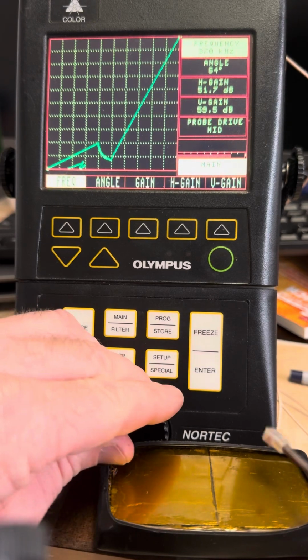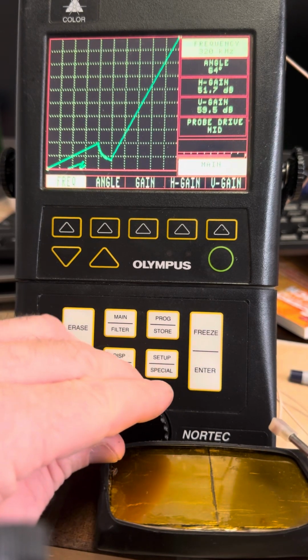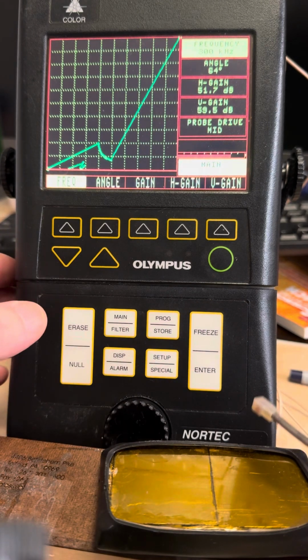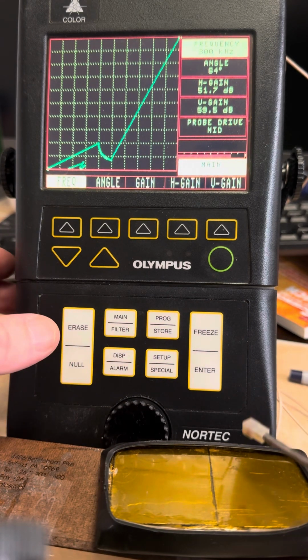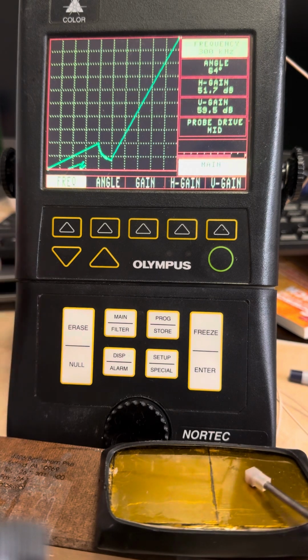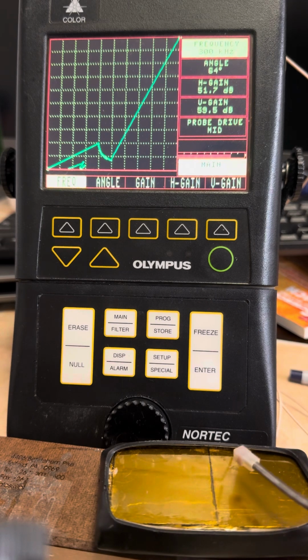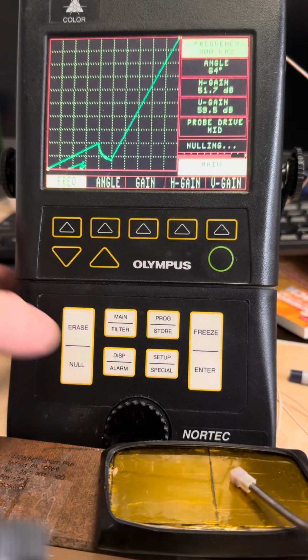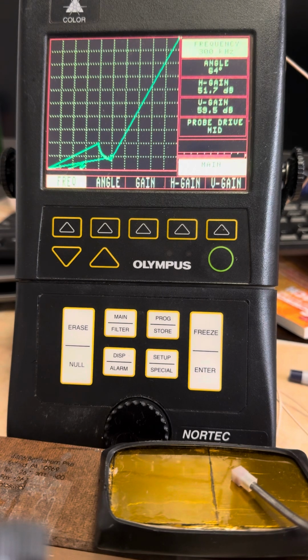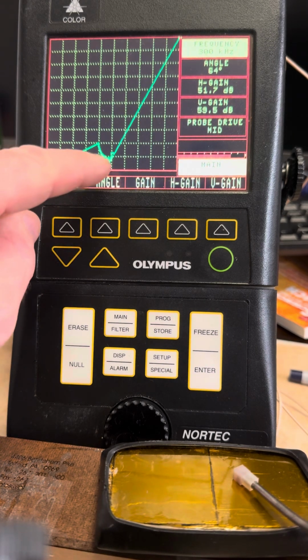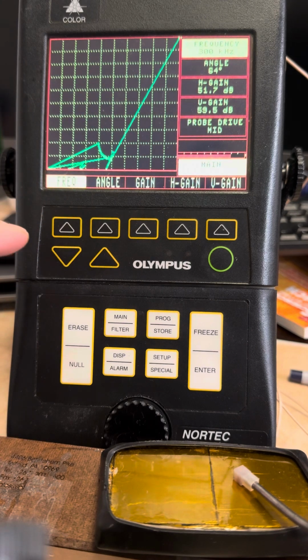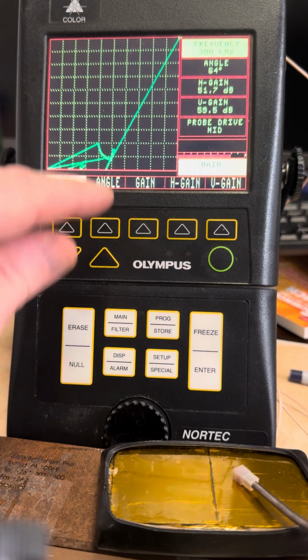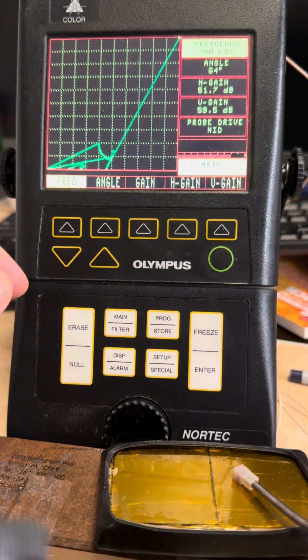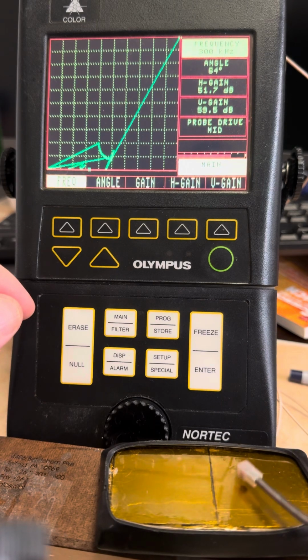Since you're looking for surface cracks, you're going to find them with a wide range of frequencies, but I'll just use 300 for this example. Place our coil back on the material. You notice now you can't see the impedance point anywhere. It's because you changed the frequency. So when you hold the coil on the material and hit null again, it's going to bring that impedance point back onto the screen. Now the reason the impedance dot is at the bottom and not in the middle is because I've selected the null point to be at the bottom. I can adjust that if I want to, but right now we're going to focus on setting the liftoff horizontal.